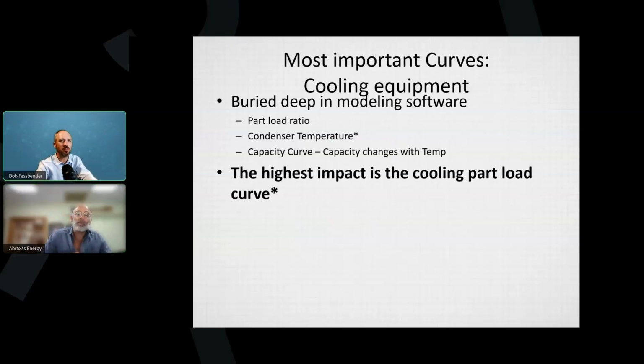Okay. I was thinking he was saying simultaneous heating and cooling, because that could be very difficult. If you're saying one season versus the other, yes, there are some inputs that will make one go up and the other one go down. For example, if you raise your plug loads, cooling goes up, heating goes down. Yes. And another big input I found that has a huge effect that you wouldn't expect is the deadband. That will increase the heating or cooling a lot. So the deadband, meaning, how often are they going? Well, I'll just leave it at that. It depends on the software. My experience is with a program you probably never used called Market Manager, which is long dead. But that was a huge input on affecting the energy savings model.